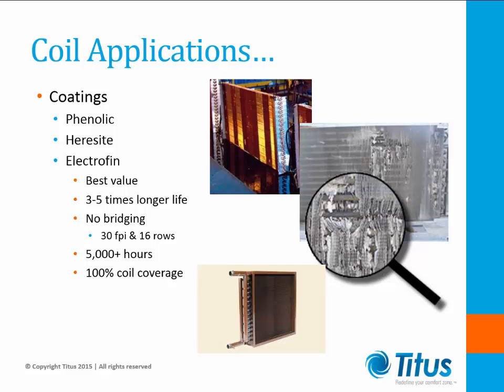A third choice for coating application for coils would be the electrofin process. It typically has the best value and lasts 3 to 5 times longer. Some of the benefits of the coating are no bridging, which can represent some coils with 30 fins per inch and 16 rows deep. It has a 5,000-plus hour salt spray rating, and it's the only coating that can provide 100% coil coverage.